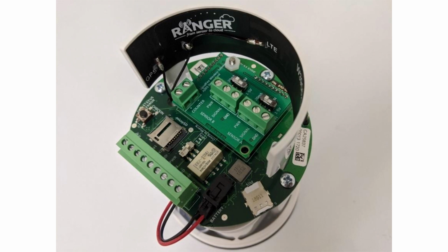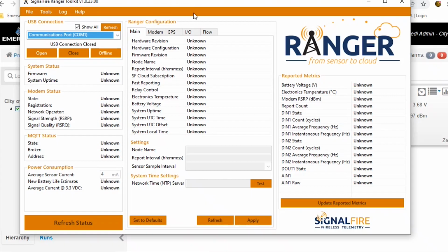Let's get started. First steps on beginning the Ranger with analog daughter card. After the card is attached, before anything is powered up, verify that your SIM card is in. Analog switches selected to voltage or milliamps dependent on transmitters. After that is done, go ahead and plug in the battery and tie in your mini USB connector.